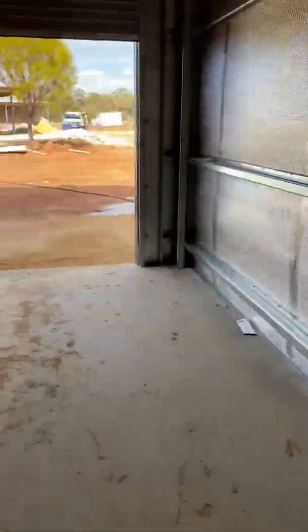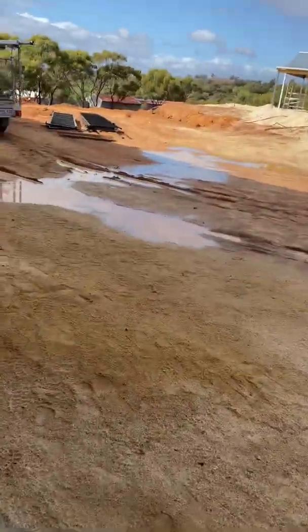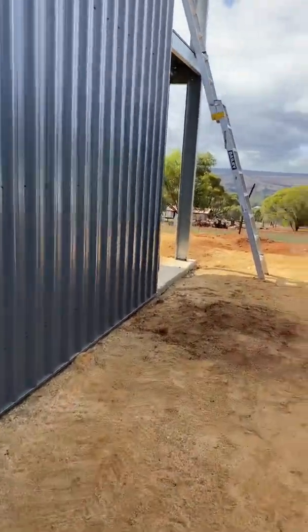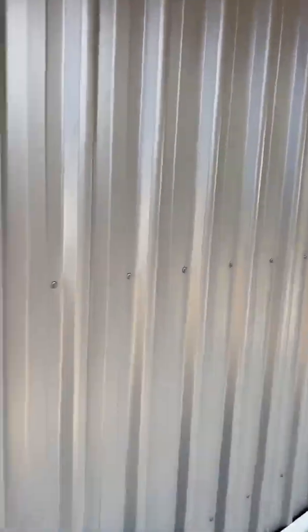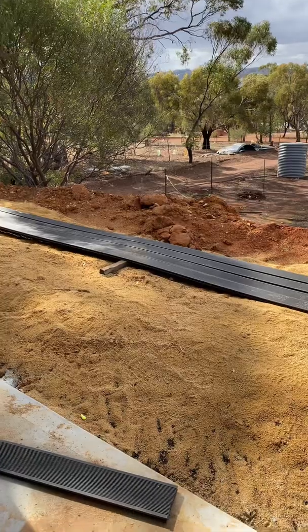This is a shed — a nice big shed. I've already done all the railing up on the roof, ran the cables, and the off-grid system is going to go there with batteries next to them. I've already built the off-grid system with the inverter and the Tesla gateway back in my workshop. That's connected and online at the moment, and Tesla support will be following up on an email I've sent them to set up the gateway for off-grid. When you're doing off-grid with Tesla, their support team needs to go in and set up the parameters — that's not something we can do as an accredited installer. They do that themselves, then we do the final setup and commissioning once it's all on site ready to go.